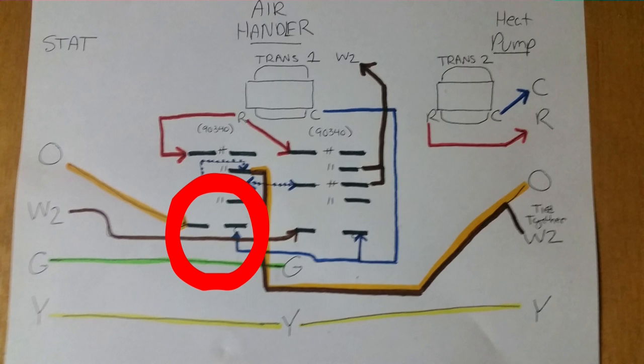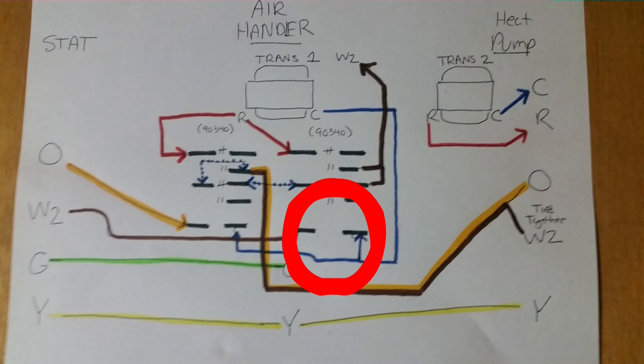The coil on the left is energized by O and common. The coil on the right is energized by W2 and common. And sometimes that will be W2 slash auxiliary. You can mate the W2 and emergency heat wires together on the thermostat just like we used to do in the past. That's not a problem.